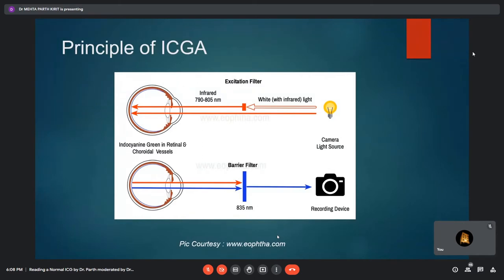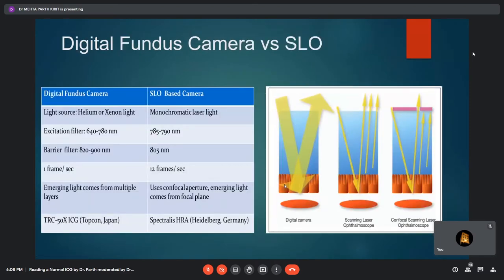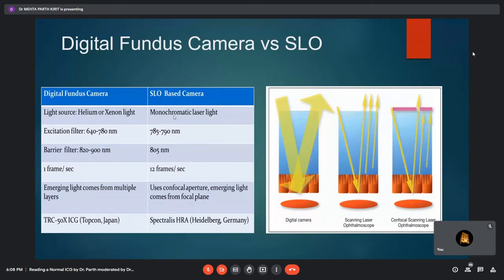The basic principle of ICG is similar to that of fundus fluorescein angiography: light passes through an excitation filter and the emitted light is passed through a barrier filter, with visualization done via the recording device. The visualization system can be a digital fundus camera or scanning laser ophthalmoscope. In a digital fundus camera, the light source is xenon or helium, whereas in SLO a monochromatic diode laser is used. Confocal SLO gives better quality pictures as emitted light is passed through a pinhole, and the SLO-based camera captures about 12 frames per second, making video angiography recordings better.